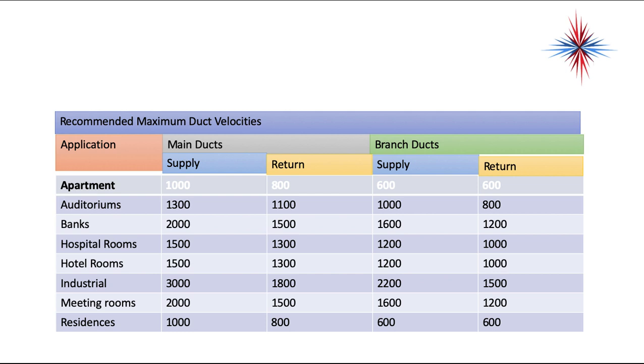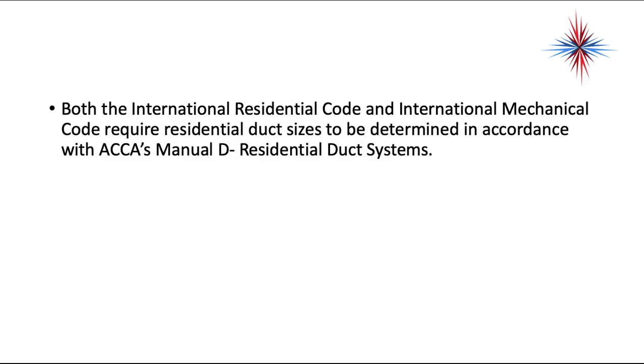Velocity also has a lot to do with duct pressures and CFM, which we'll talk about in a minute. Both the International Residential Code and the International Mechanical Code require residential duct sizes to be determined in accordance with ACCA's — Air Conditioning Contractors of America — Manual D Residential Duct Systems. This is code; ductwork has to be sized appropriately.